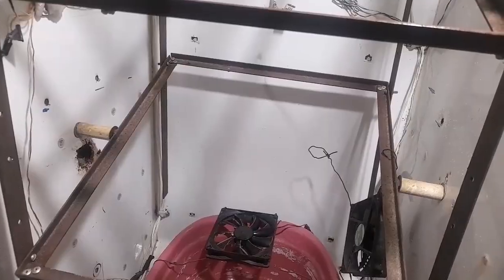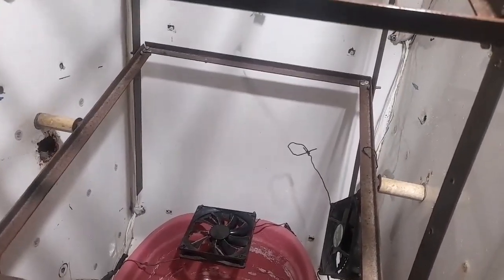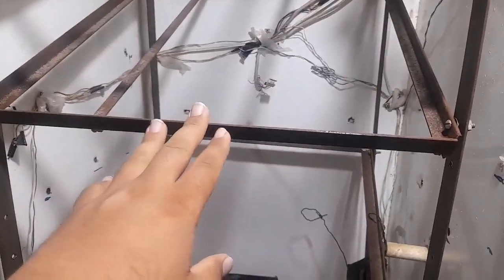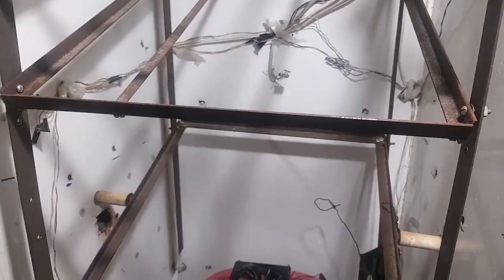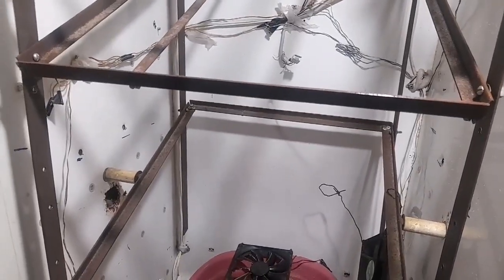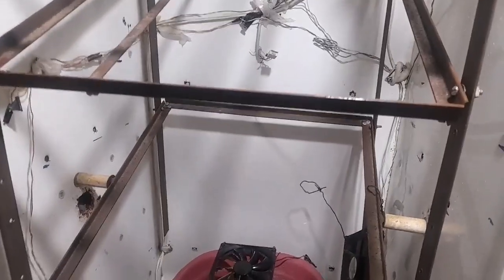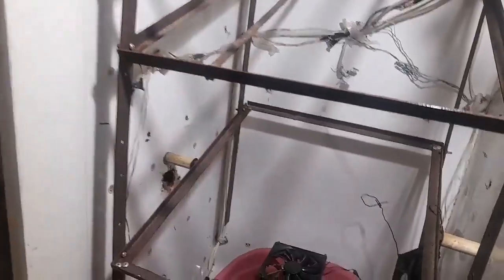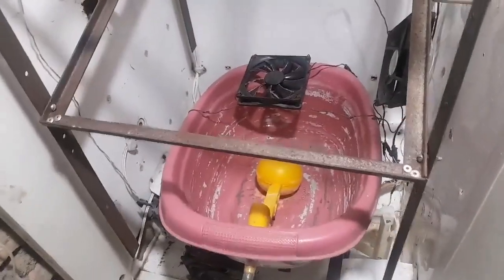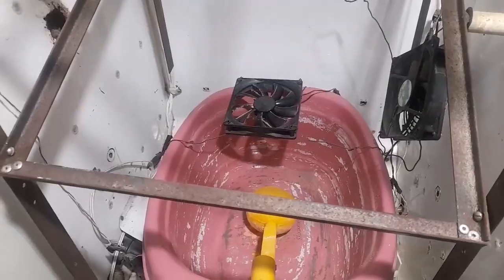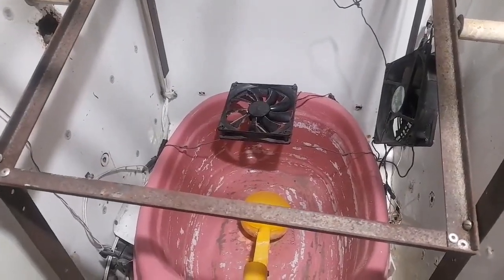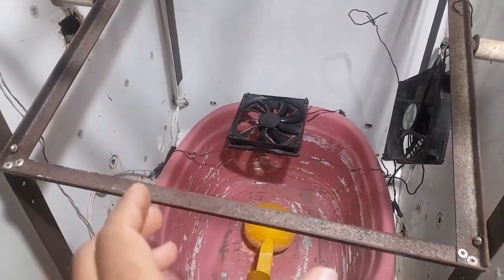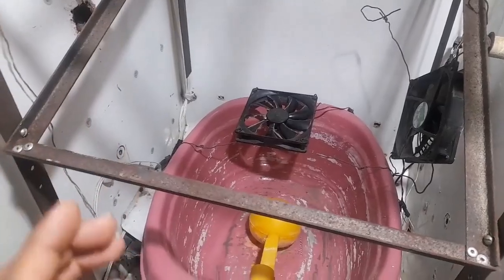Another advantage of this method is that it doesn't create the excessive moisture associated with ultrasonic humidifiers. If you've ever used an ultrasonic humidifier inside a metal incubator, you've probably noticed corrosion or rust forming on exposed metal parts after some time. With this airflow-based system, that problem is greatly reduced. The incubator stays cleaner, drier, and much more reliable over the long term.